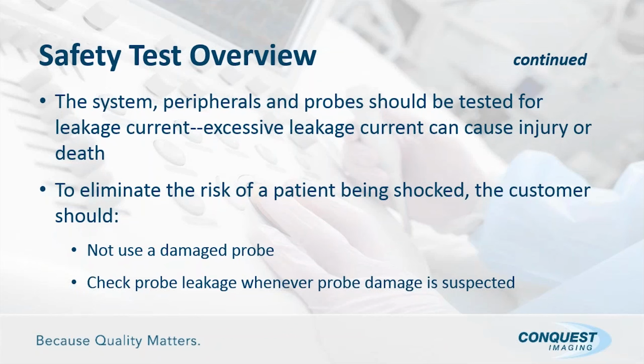The other thing that I find interesting is I've traveled all over the nation to many hospitals, and the one thing that they don't seem to check is the probes. And that's kind of funny to me because that's the one place that we actually take the probe and place it on the patient and give it the path. If in your hospital you're not currently testing your probes, I think you're really opening yourself up to some real problems, because that to me is where the rubber meets the road from an electrical safety standpoint.